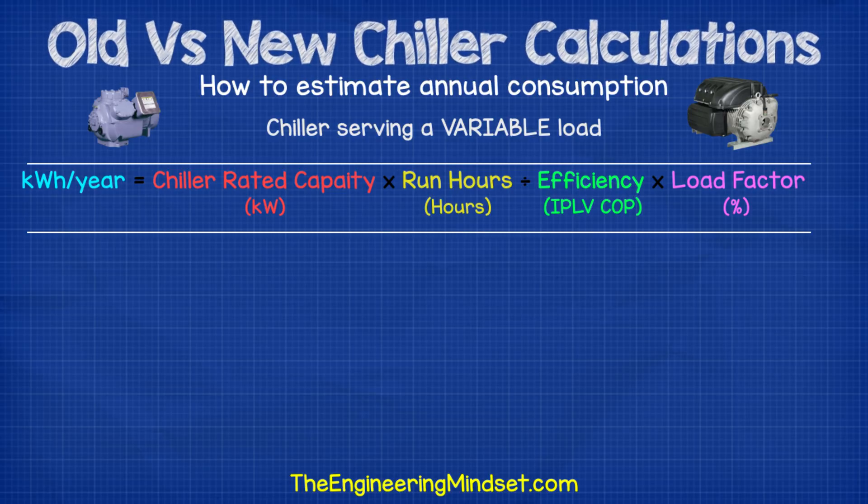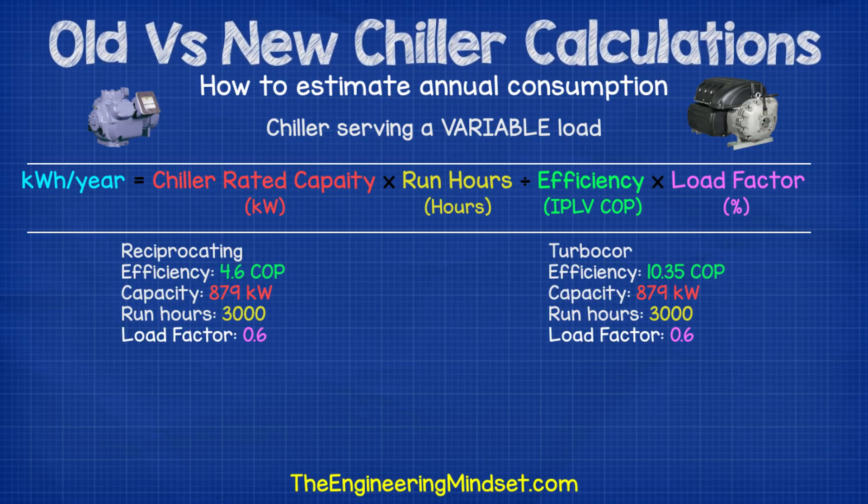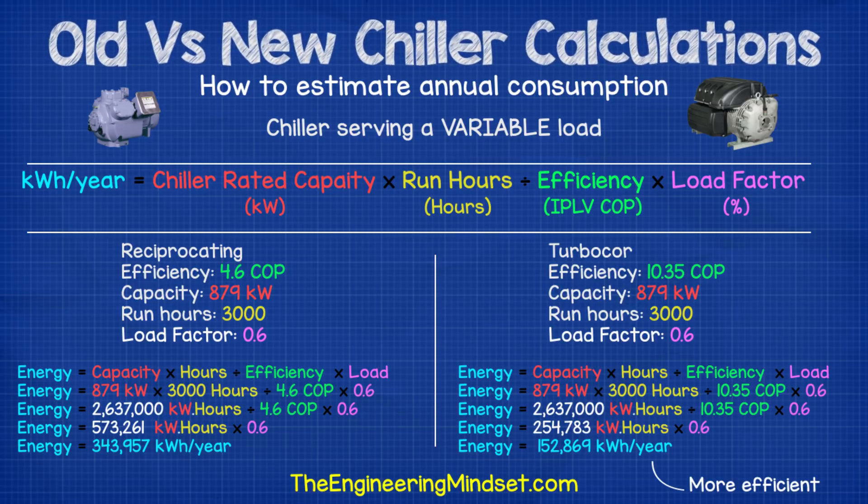If you have the IPLV COP value, take the cooling capacity in kilowatts, multiply by the operating hours per year, divide by the IPLV COP efficiency, then multiply by the average load factor — again typically around 60%. For example, comparing a Turbocor chiller with an IPLV COP of 10.35 to a reciprocating chiller with an IPLV COP of 4.6, both with an average load factor of 0.6 running 3,000 hours per year — the reciprocating chiller consumes around 343,000 kilowatt hours per year whereas the Turbocor consumes around 153,000 kilowatt hours per year.